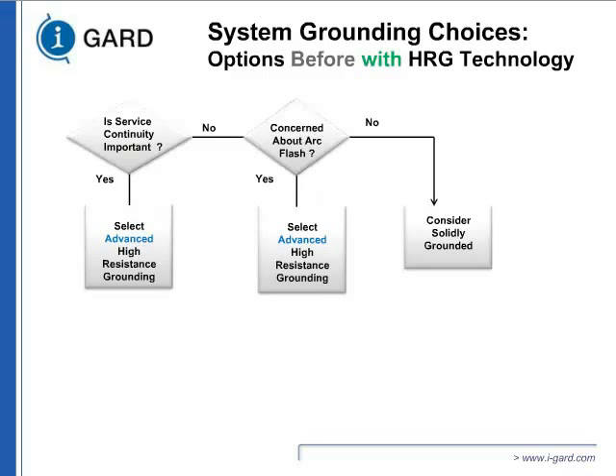When you go to advanced, you can get a second fault priority, and you can see in the risk analysis how it reduces the risk. If 90 to 98% of first faults are ground faults, and you remove that fault, the probability that a second fault will happen at the same time goes down further. Now, nobody can tell you it will be 100% effective. There's no 100% probability. But with second fault priority, it's pretty close, unless there is a human error. If your process continuity is not important and you don't care about arc flash, of course, solid ground is still an option.